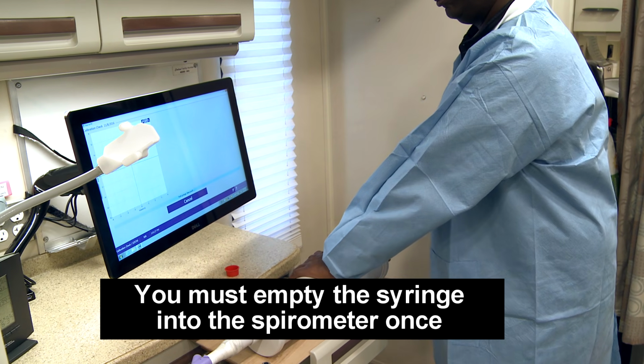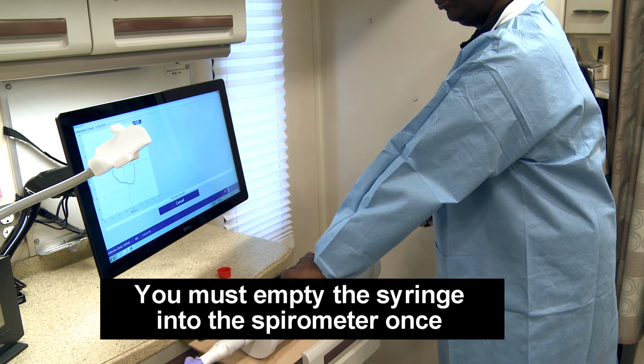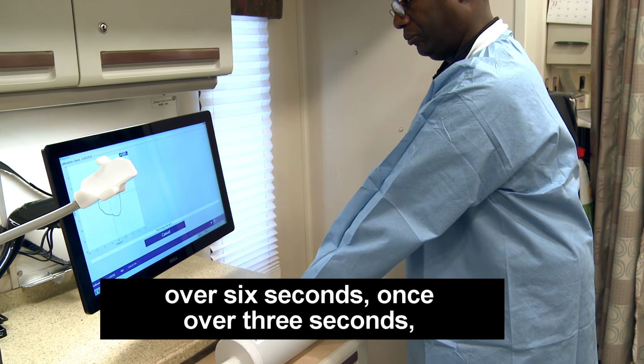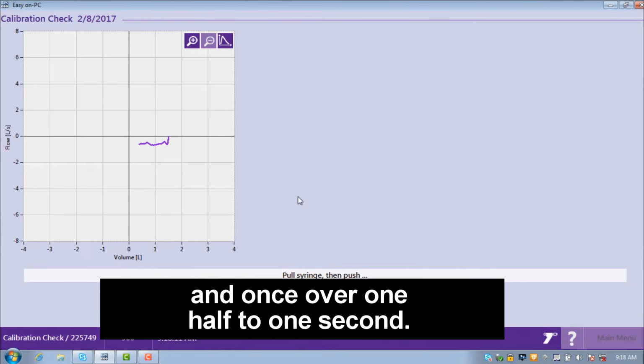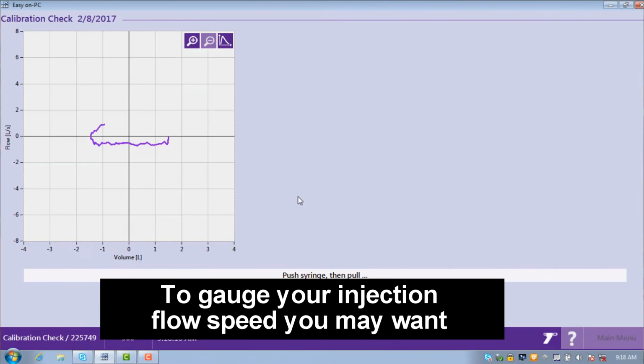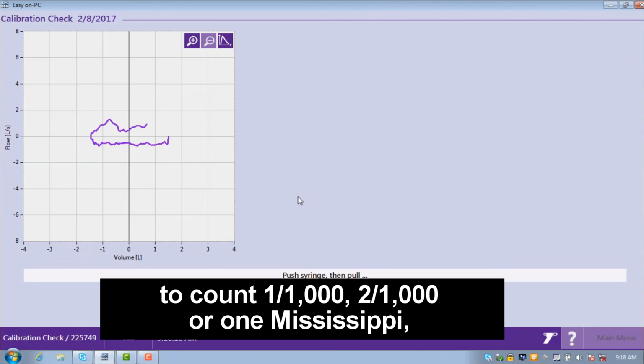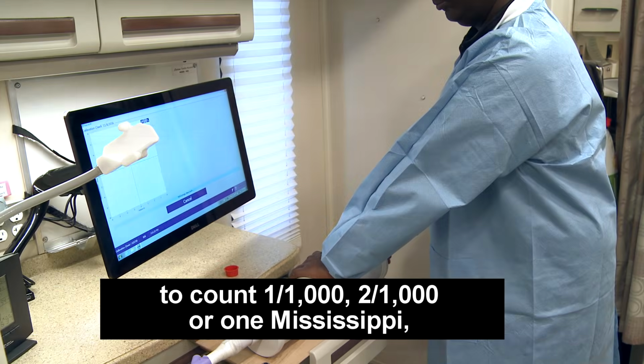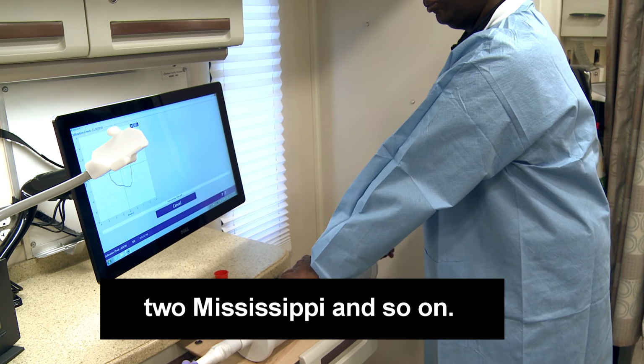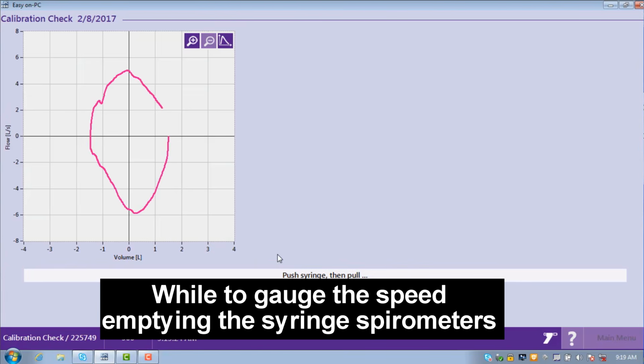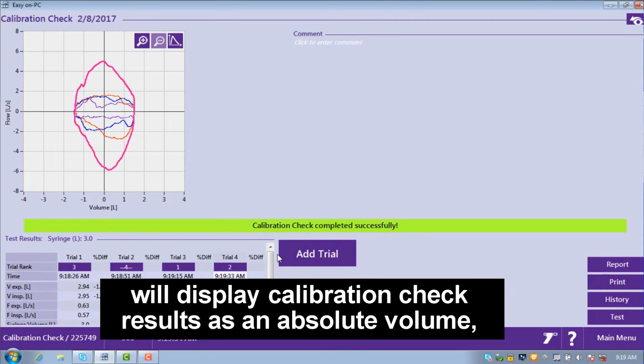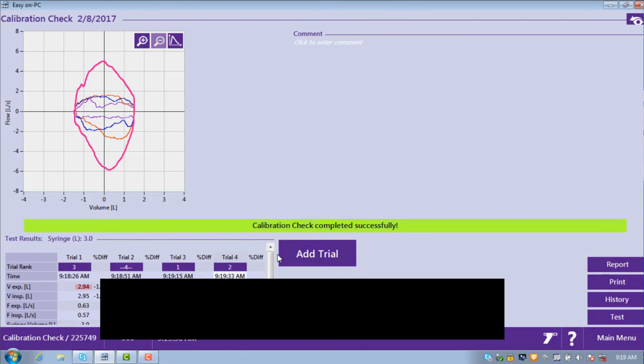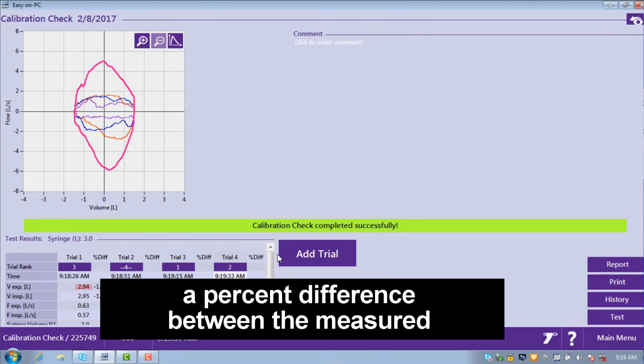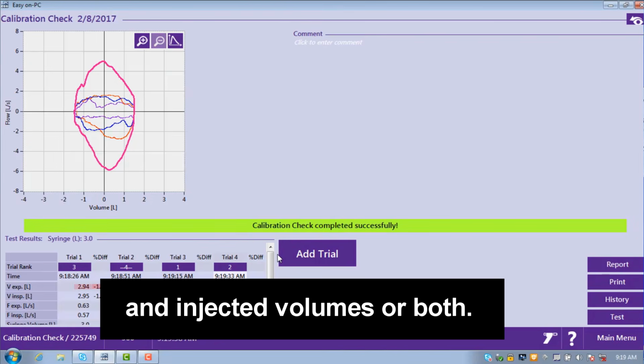You must empty the syringe into the spirometer once over 6 seconds, once over 3 seconds, and once over 1/2 to 1 second. To gauge your injection flow speed, you may want to count 1 1,000, 2 1,000, or 1 Mississippi, 2 Mississippi, and so on. Spirometers will display calibration check results as an absolute volume, a % difference between the measured and injected volumes, or both.